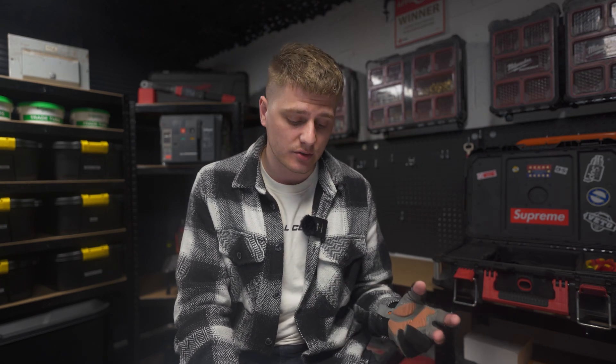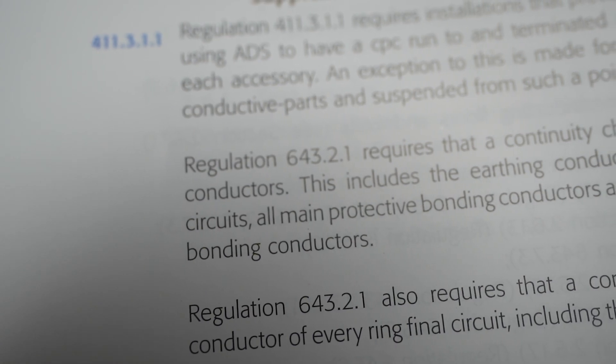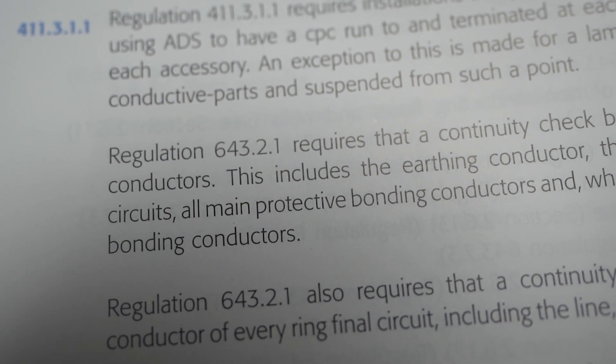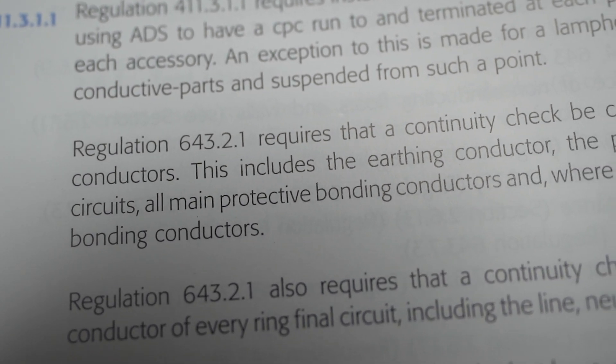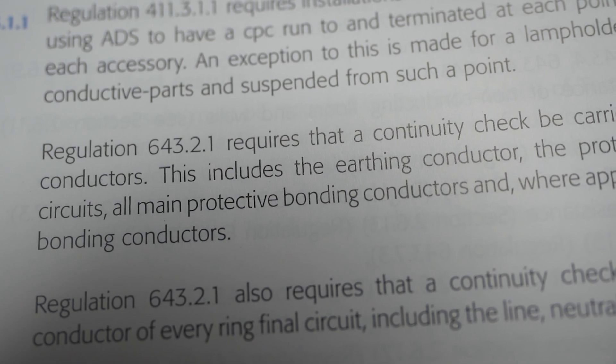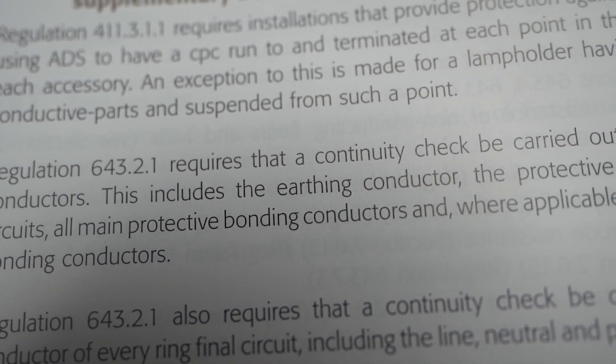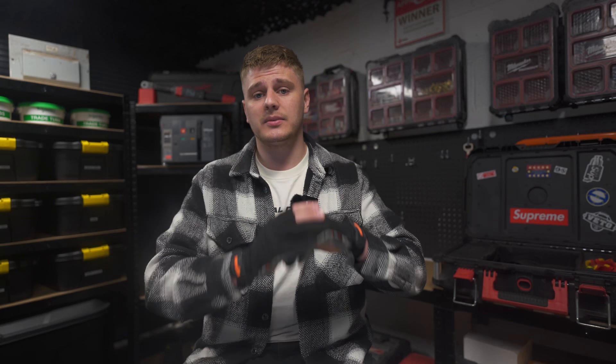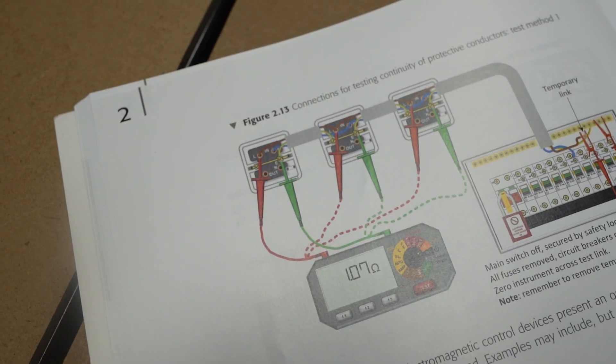The second thing we're required to do as electricians is regulation 643.2.1, which requires that a continuity check be carried out on all protective conductors. This includes the earthing conductor, the protective conductors of all circuits, all main protective bonding conductors, and where applicable, all supplementary bonding conductors as well. So not only do we need to make sure there's a CPC at all points of the circuit and all accessories, but we also need to test it at all points to verify its continuity.